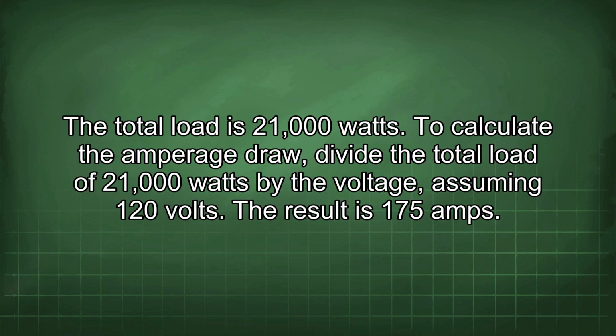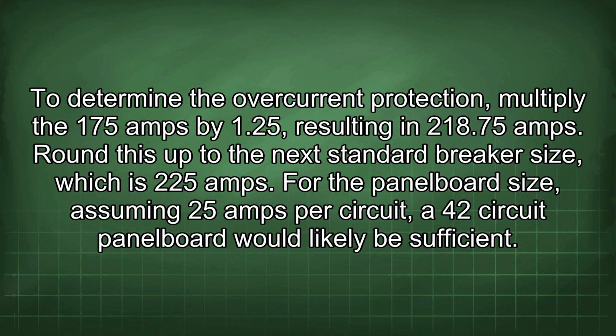The total load is 21,000 watts. To calculate the amperage draw, divide the total load of 21,000 watts by the voltage, assuming 120 volts. The result is 175 amps. To determine the overcurrent protection, multiply the 175 amps by 1.25, resulting in 218.75 amps. Round this up to the next standard breaker size, which is 225 amps. For the panel board size, assuming 25 amps per circuit, a 42-circuit panel board will likely be sufficient.